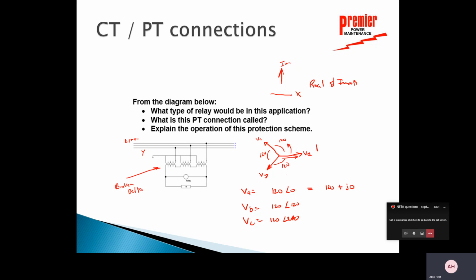If I look at VB down here, I can see that it turns out to be minus 60 volts and a minus 104. So if I look at this diagram, I go over 60 and down 104, and that would be the same point as the end of this arrow. And voltage C would still be minus 60, because I'm going over to the left 60, but I'm going up 104. So the bottom line is if I add up VA plus VB plus VC, 120 minus 60 is 0. 0 plus 104 minus 104 is 0. I get 0 volts.